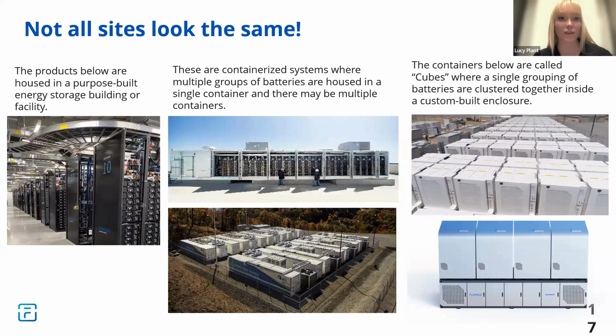Battery chemistry is another area where we've seen a lot of innovation, moving from LFP toward sodium ion, and some new flow technology coming in as we continue to innovate in that space. Even in the last few years, systems have moved away from NMC, nickel manganese cobalt cathodes, toward lithium iron phosphate, or LFP, chemistry. LFP is thermally more stable and less likely to go into a thermal runaway state, and we continue to see innovation as we look toward sodium and other new chemistries.